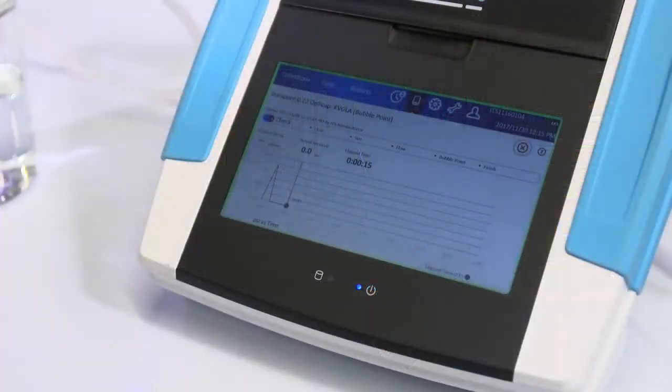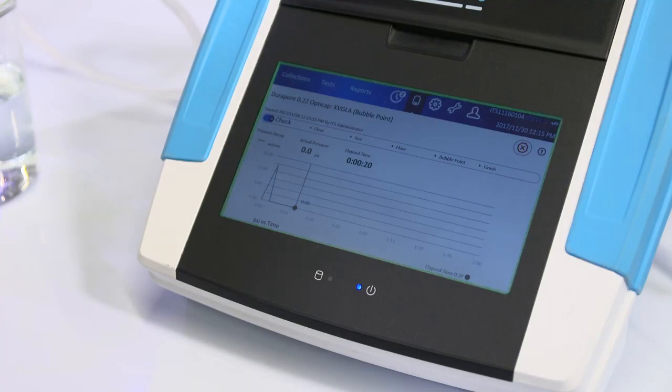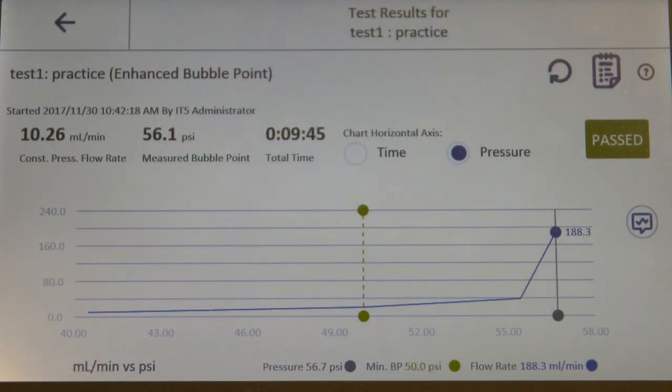Test progress can be monitored during the test. All integrity test instruments typically display some combination of system pressure, pressure decay, or gas flow rate during the test. By monitoring the pressure or flow trends, you can check for problems.